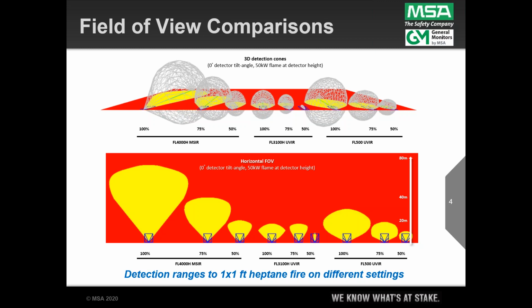On the left side of this lower panel of field of view comparisons, we've got the MSIR, the multi-spectrum IR. It's our model FL4000H, and the 100% label is the highest sensitivity setting. And this is all, by the way, I should have prefaced this, the detection coverage in response to a 1 foot by 1 foot square pan fire of heptane, which is the primary constituent of gasoline. Factory Mutual used to use gasoline, then they realized they had variability problems in the spring, summer and winter blends, and it was also different geographically. So heptane is a repeatable fuel regardless of your location, and if you wanted to replicate these performance tests, you could, and because they're audited, you should be able to get the same results.